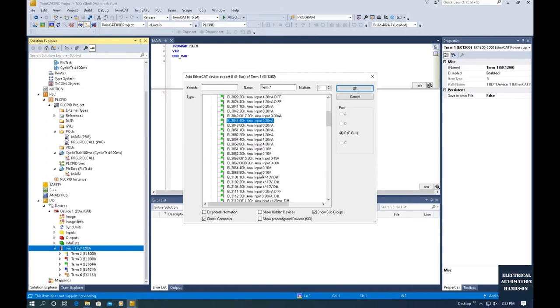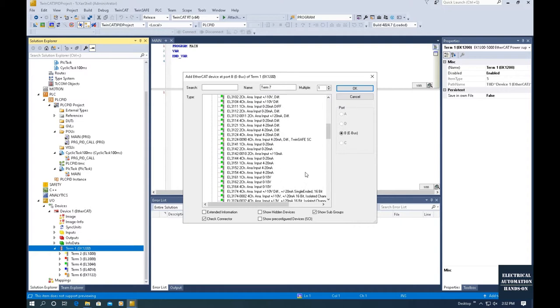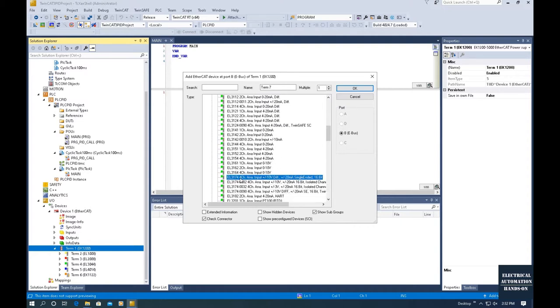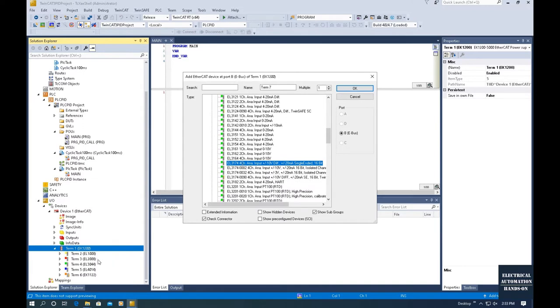To receive voltage channels, we can also use the EL3068, which is an 8-channel 0-10V card. But in industry, most analog sensors are 4-20mA or 0-20mA. Another commonly used analog card is the EL3174 — it has 4 channels, and based on your application you can select either voltage or current channel. Its resolution is 16-bit, making it a high-resolution card. I will mainly introduce the EL3174, and I will add it to the project since it can measure both voltage and current channels.